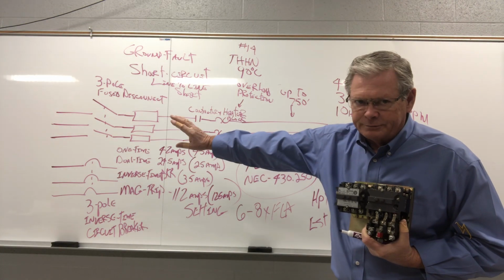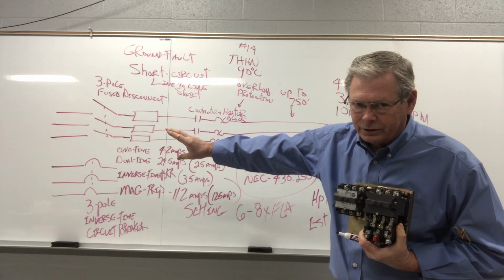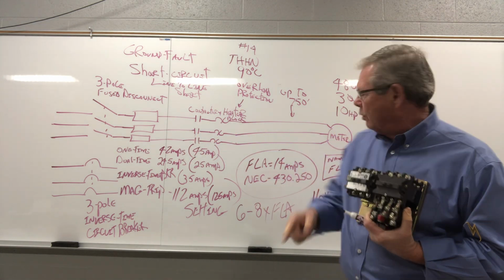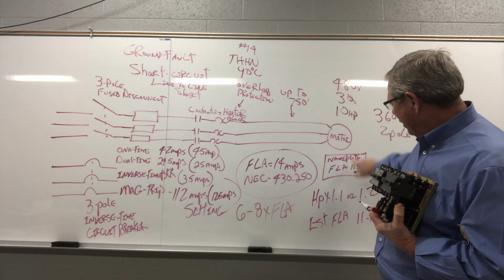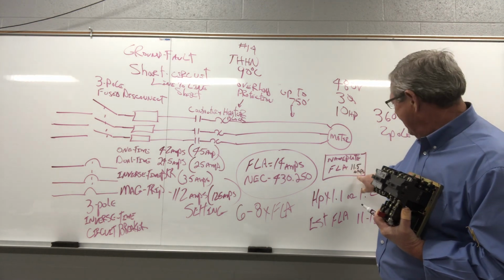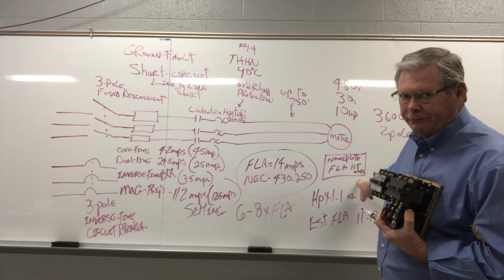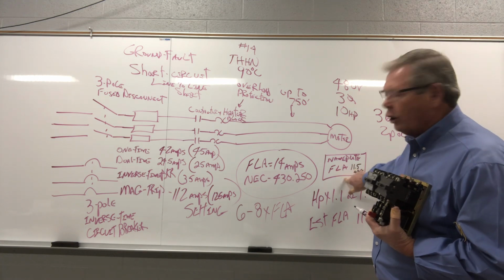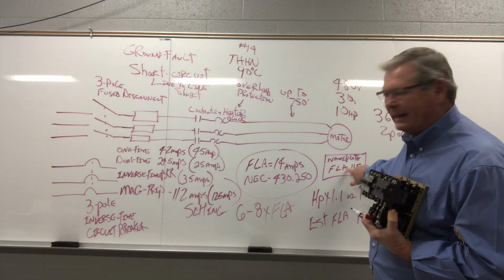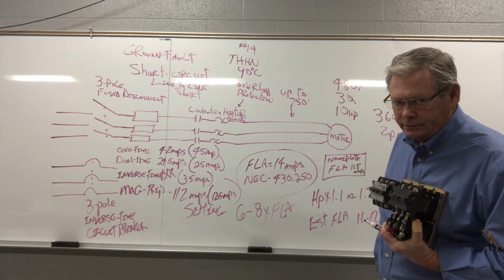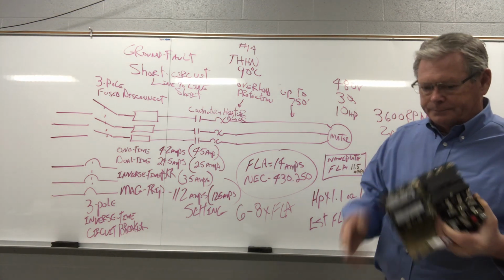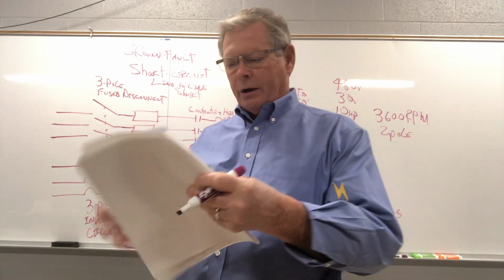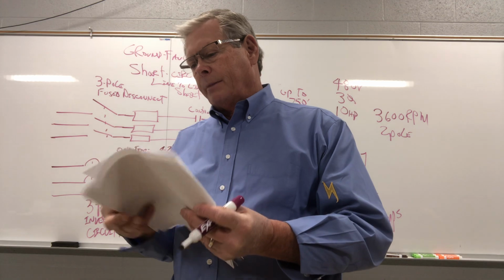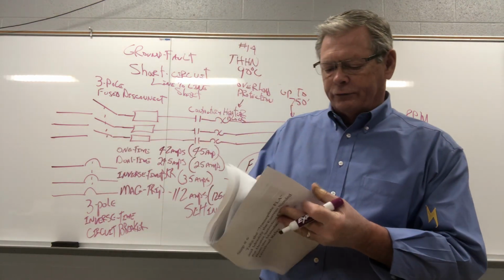Everything we've done up to now has been for any 10 horsepower motor we hook to this circuit. Now we are going to say we have a GE motor with an FLA of 11.5 amps. This is the first time we've done this. We're going back to the nameplate and get what this motor draws. So, now we're going to deal with our overcurrent, our overload protection. And remember, overload means when we ask for too much horsepower off the end of that shaft.